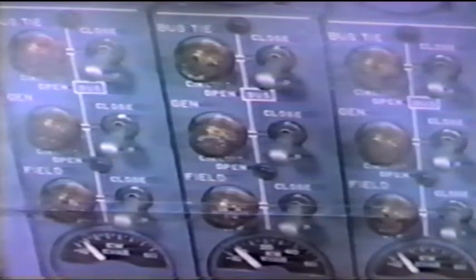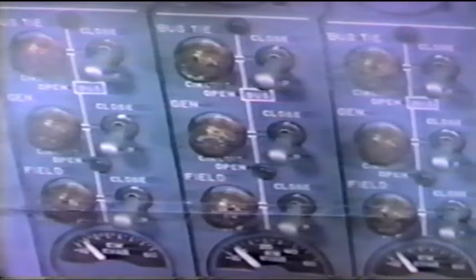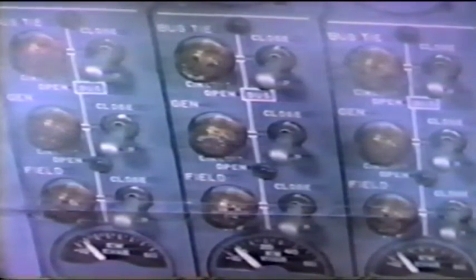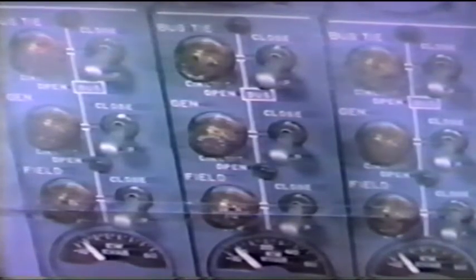You'll notice just below the generator breaker there's a small screw, and we call that the essential screw. And that is because regardless of whether or not the generator breaker is closed, we can draw essential power from that generator if the field breaker is closed. Now, I know you're probably thinking an essential screw is something completely different on long layovers, but for 727 electrical system purposes, we'll call this the essential screw. We'll see how this ties in when we talk about the essential AC system.